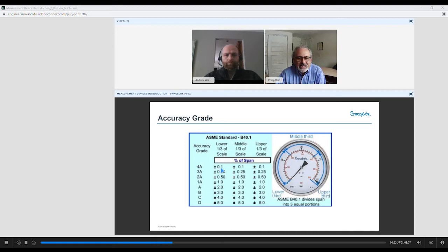So if you have plus or minus 0.1% of span, what that refers to, they take 5 separate readings on this gauge. And the percentage of span, it has to maintain accuracy to within 0.1% of span. If you were in a D class gauge, it would be plus or minus 5% of span. So being arbitrary here, if we had a 0 to 100 PSI gauge, we may be at 105 or 95 if we're using an accuracy grade D. Most of our gauges are a 1A class, and they would have a plus or minus typically 1% of span or better.